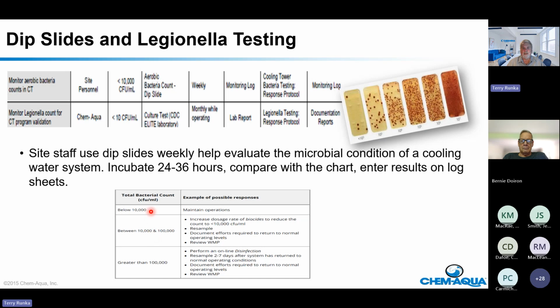If you get less than 10,000, there's nothing you should do. If you get 10,000 to 100,000 on your dip slide, you want to check your biocide program - make sure the pails aren't empty, the pumps are primed, that it's actually getting in. And if you get over 100,000, then you should do a quick online disinfection - we'll help you with that, and you have protocols for that.